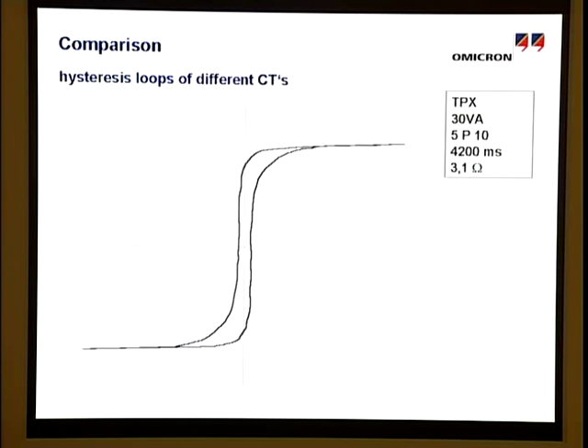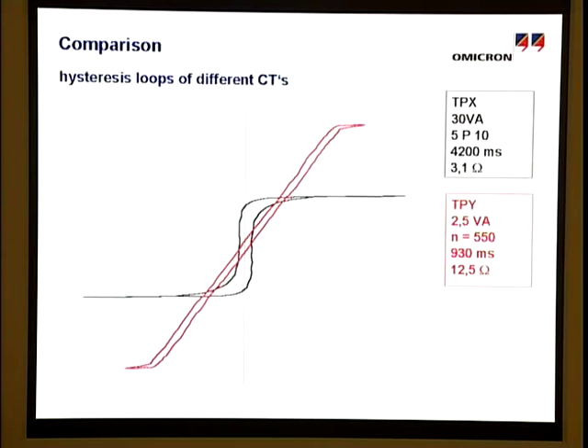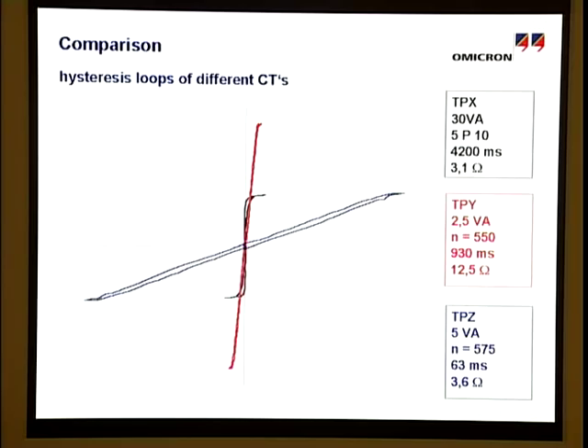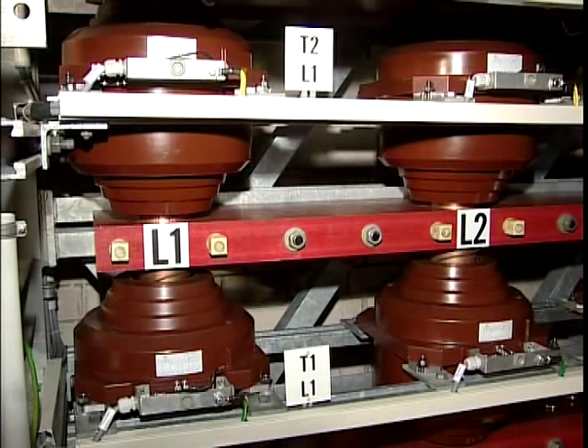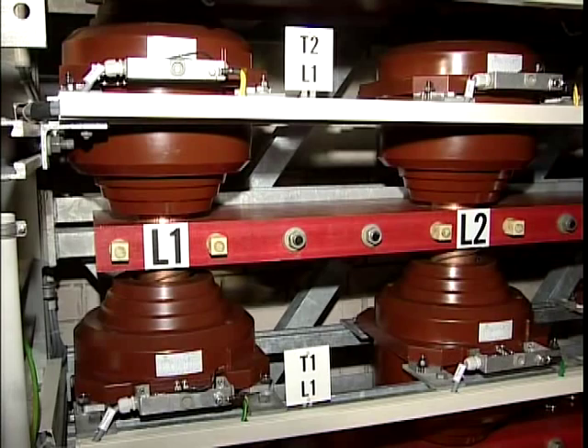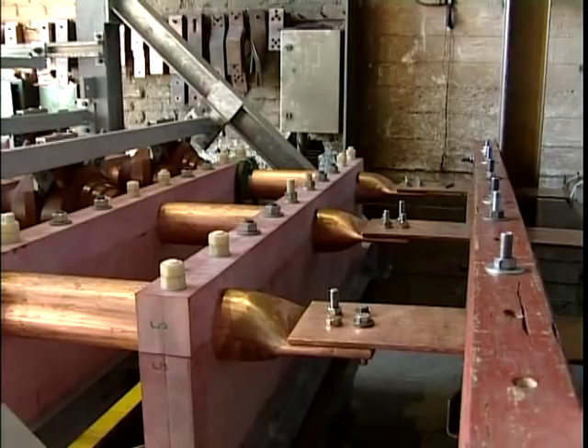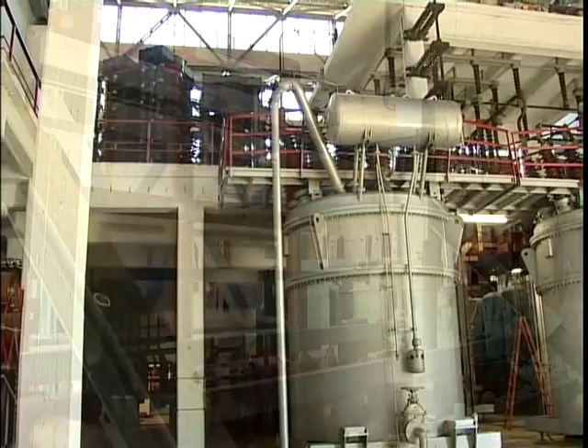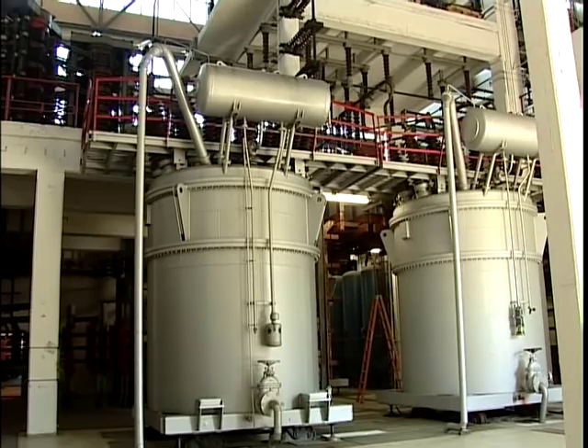Making use of an anti-remanence core or linear characteristic CTs with air gaps was discussed as a possible solution. With regard to this special application, the theoretical calculations, particularly with consideration of the thermal stress caused by the tests, were to be confirmed. For this, the designed current transformers were installed in the laboratory of the Institut Prüffeld für Elektrische Hochleistungstechnik GmbH. The necessary short circuit currents can be adjusted automatically in amplitude, phase angle and DC offset by coils and resistances controlled remotely via PC.